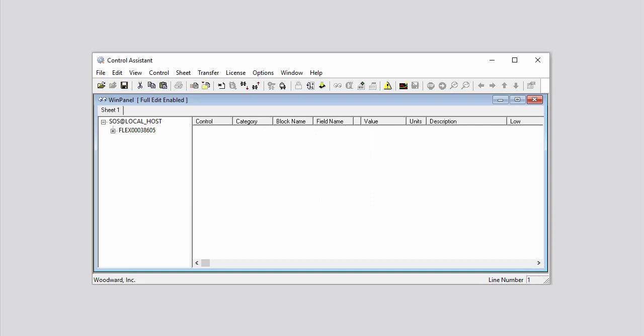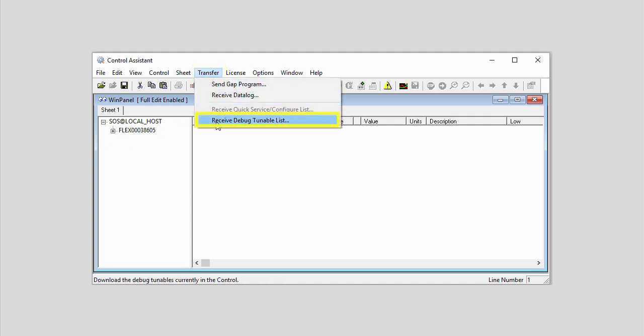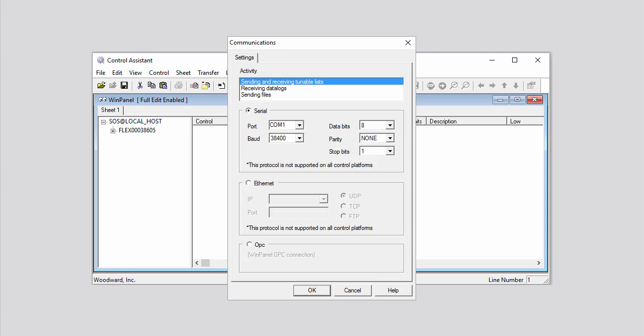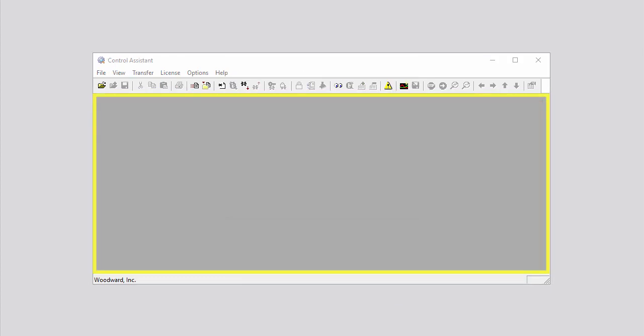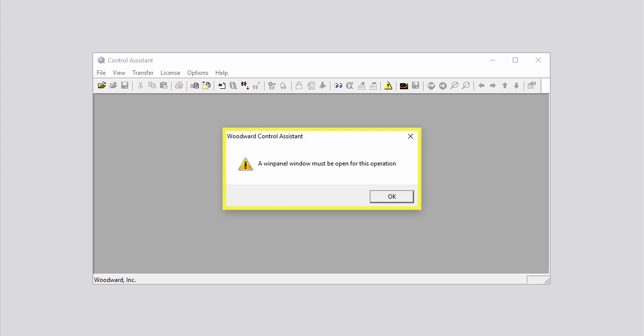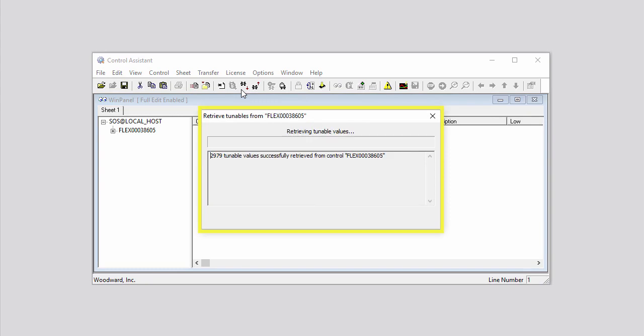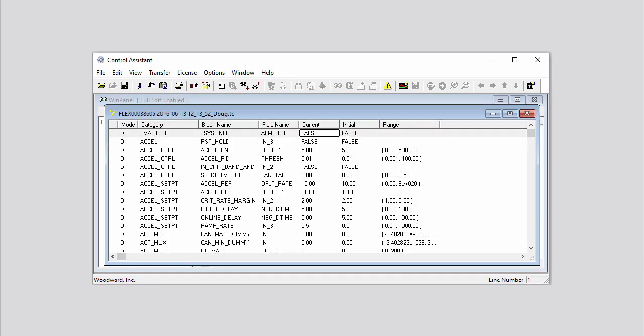Now you can receive a debug tunable list from the controller. To do this, either click Transfer on the menu bar and then click Receive Debug Tunable List from the drop-down menu, or click the Receive Debug Tunable List icon on the toolbar. If the Communications dialog box opens, click the OPC radio button, then click OK. Please note that if there is no Win Panel window open already, a Woodward Control Assistant window will pop up stating that a Win Panel window must be open for this operation — click OK to close this window. In the Retrieve Tunables pop-up window that opens, wait for the word Done to display at the top, then click Open. A new window with the controller's name opens in Control Assistant, containing the tunable configuration, or TC file.